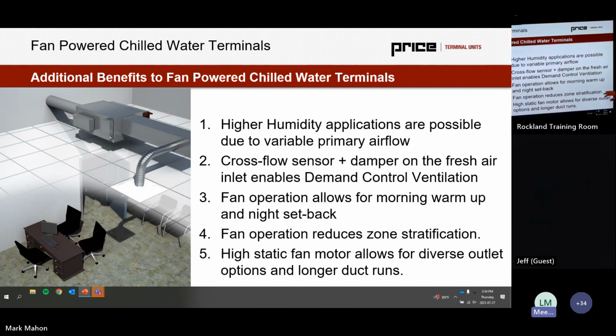Fan operation is also going to reduce that zone stratification. So I kind of referred to that, but keeping a higher ratio of fan airflow during deadband, because the EC motor has such low power consumption anyways, we can turn over a lot of airflow in deadband, which is going to keep the space mixed and keep it more comfortable for longer. It's actually often going to result in better energy efficiency because we don't stratify the space and kick in heating when we have enough heating in the zone, or kick in cooling prematurely. And then the high static for the fan motor allows for a diverse set of outlet options. So whether we want architectural slots, we can really do anything that you can do with the VAV box with this terminal. So that allows for a lot of flexibility.